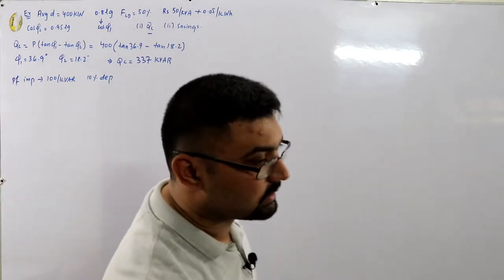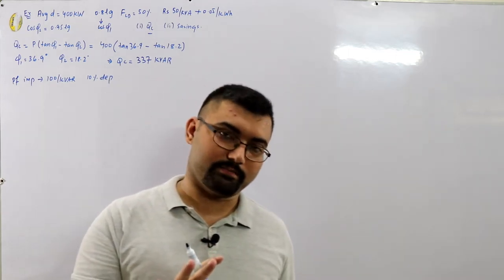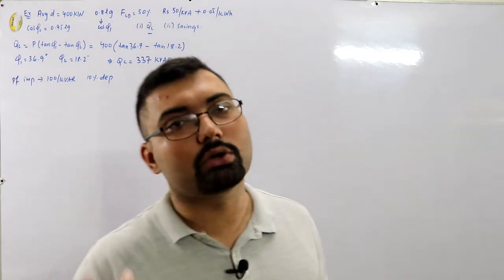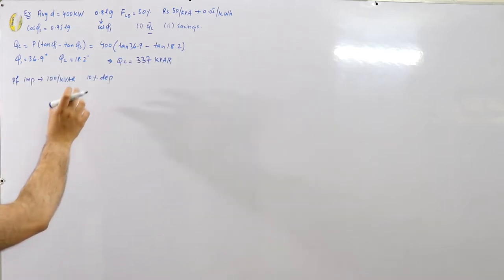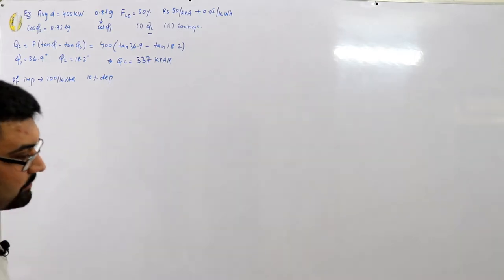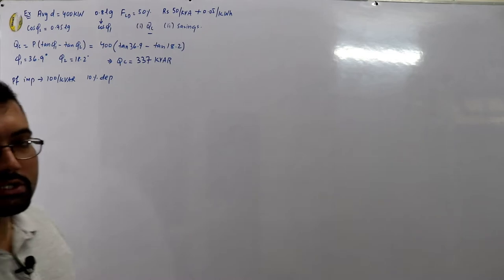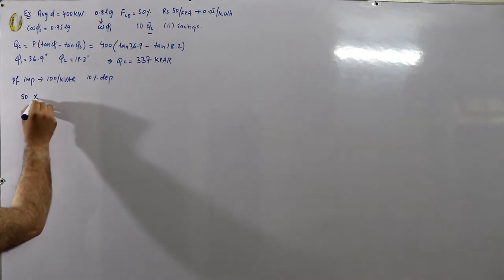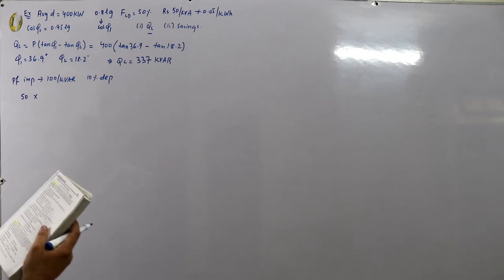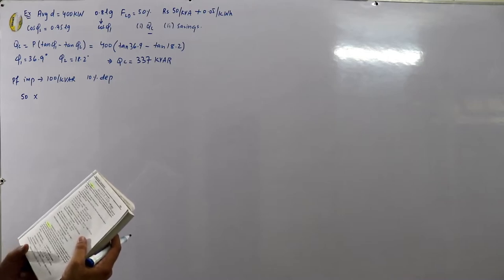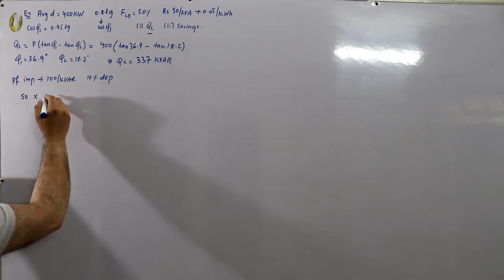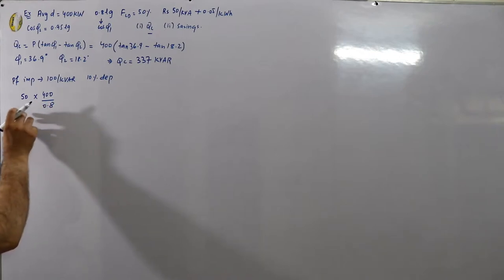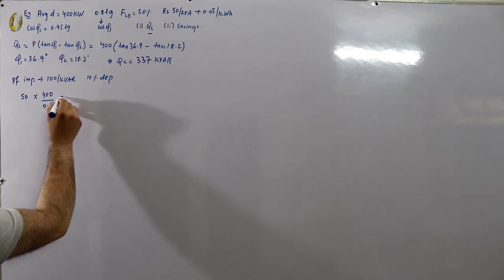The energy charges per kilowatt hour remain the same in both cases, so we don't calculate those here. Only the maximum kVA charges are changing — that is, only the fixed cost is changing. The difference is caused only by those fixed charges. The kVAs in the first case are 400 divided by 0.8, so we calculate the charges for the first case.